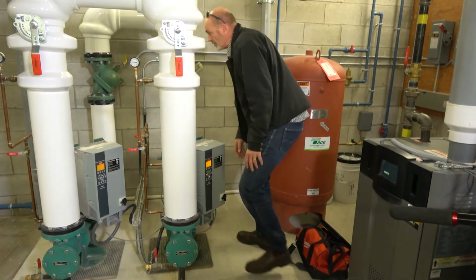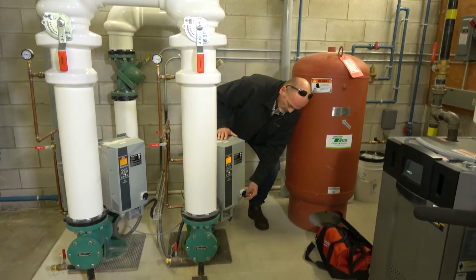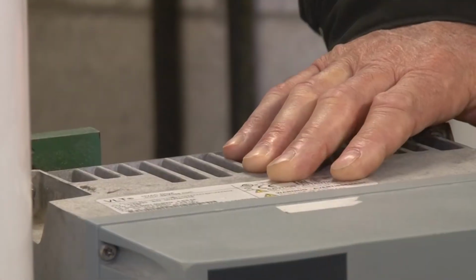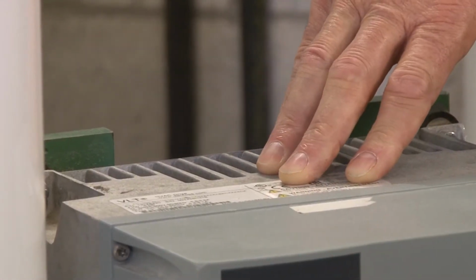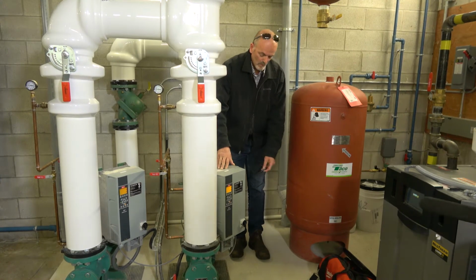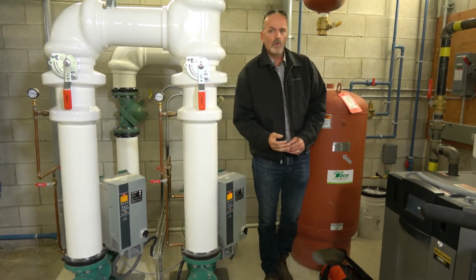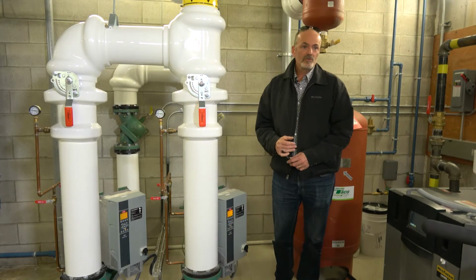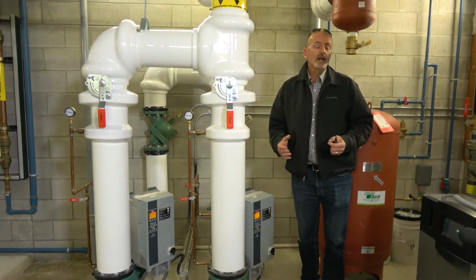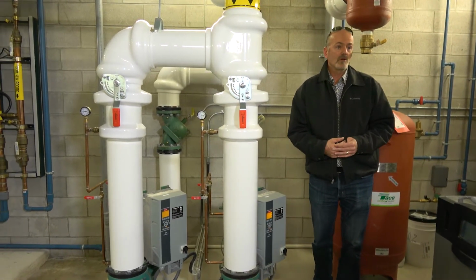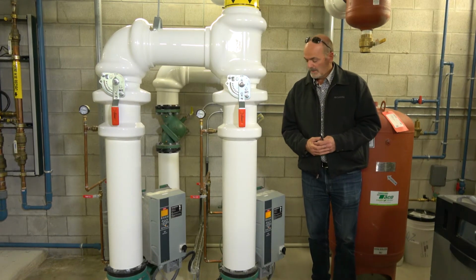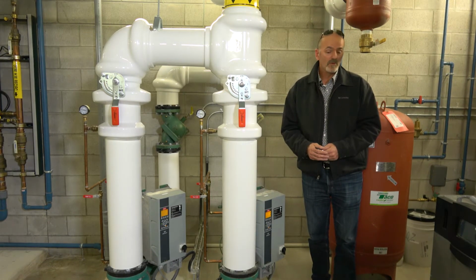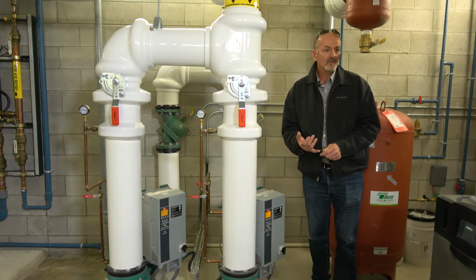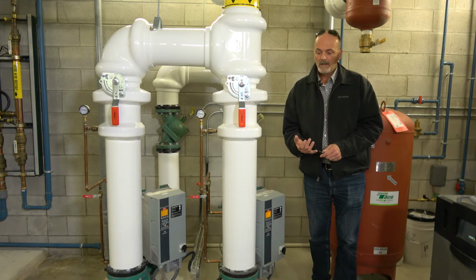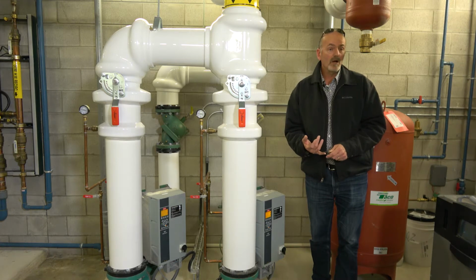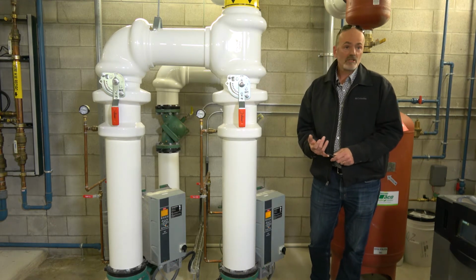Yeah, each pump has an aluminum plate fixed here. It should never be removed, because that's all the vital information on the pump. Okay, and that will give you the manufacturer's order number and the pump details so that you can allocate through your local service dealer and the wholesaler contractor the required seal kit to replace. The seal kit comes with a casing gasket, two-piece seal, shaft sleeve replacement, as well as shaft sleeve gasket.